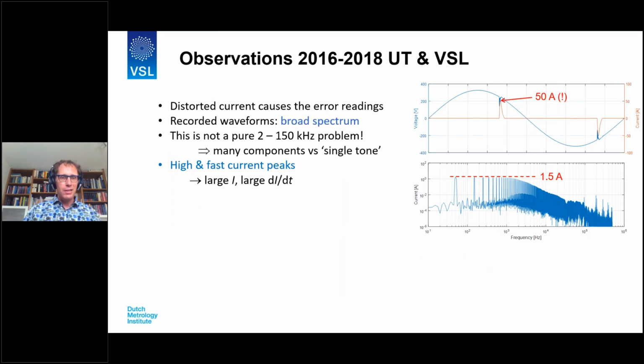First of all, the observations of Twente and VSL showed that distorted current, not voltage, causes the error reading. The recorded waveforms were very broadband, as you can see here in the figure on the right, which means this is not a pure conventional 2 to 150 kilohertz problem. The difference is that we see many components at the same time versus a single tone in the conventional measurements.